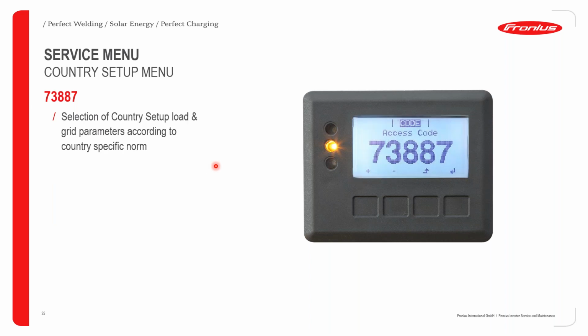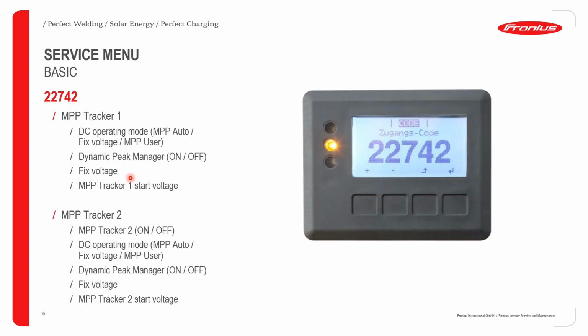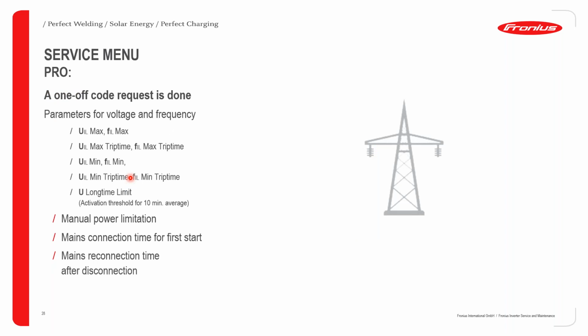Same with the country setup menu. The code is 73887. So there are different codes to access different service menus for our inverters. But then there's a special menu called the professional menu, which isn't accessible to everyone. It is only accessible to specified or trained installers or technicians, because there are sensitive settings here, and if these settings are entered wrongly, then the whole system might be in trouble. If any installer needs this code, he would have to contact our technical support for them to send a one-off code, which they would then use to access these respective settings.